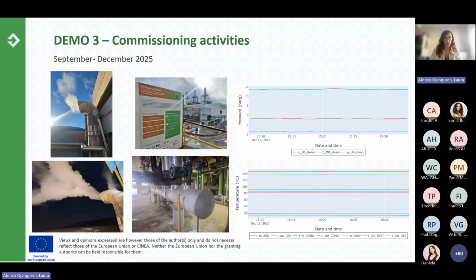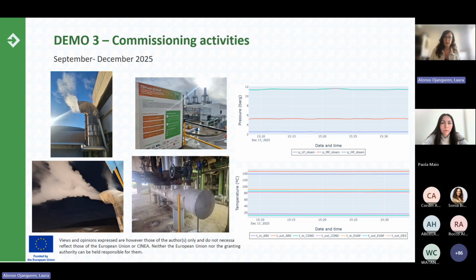And as we were making the system run in different phases, in the first phase we only used the flash tank, so we tested it producing only low pressure steam. And then we used the whole system, combining the low pressure steam with the thermocompressor and producing the whole amount of steam. As you can see the difference, we produce much more steam when the thermocompressor is used. And then the next milestone was to introduce the produced steam into the medium pressure steam header, which was successfully done at the end of last year.